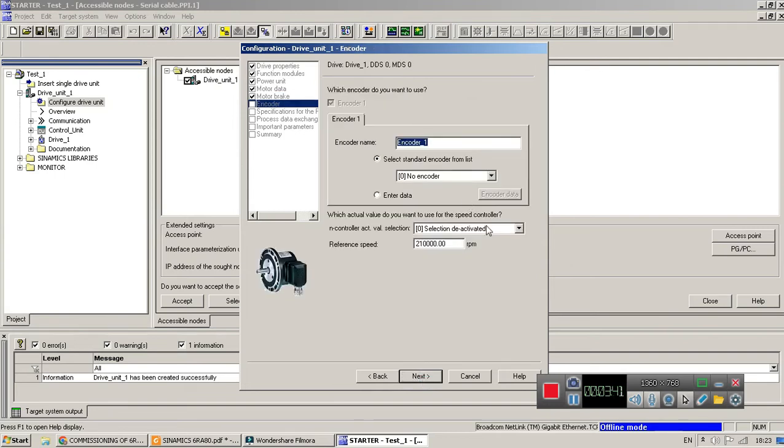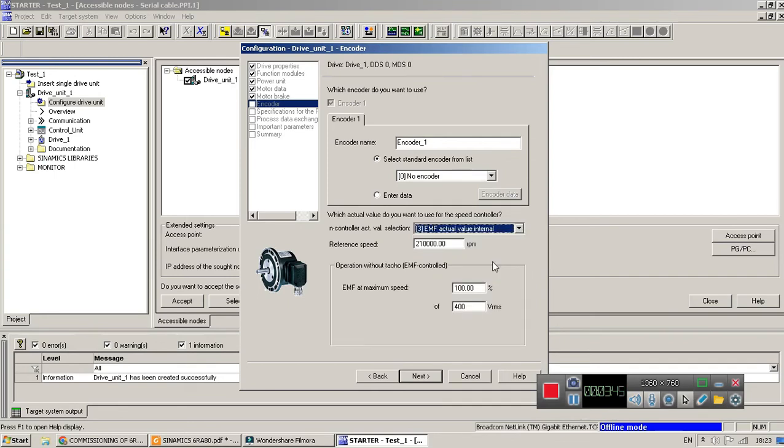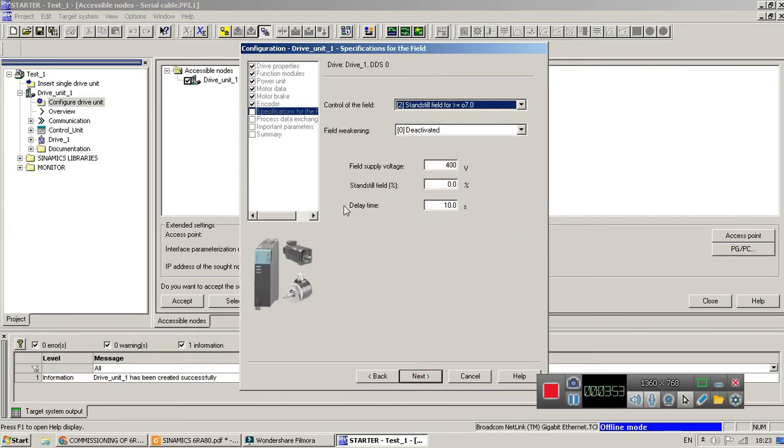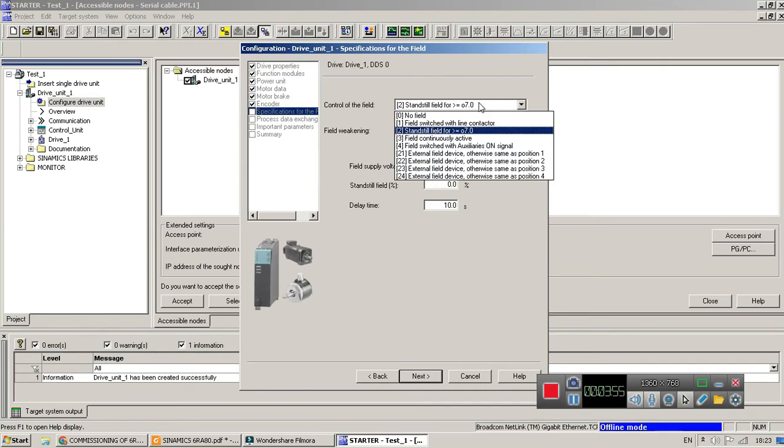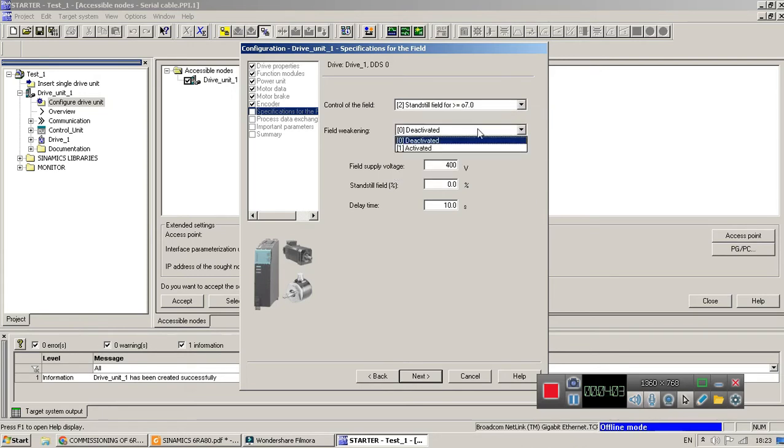Here we have selected speed feedback selection. Here I have selected EMF and the RPM of the motor, for 1500 let's suppose. Go to the next. And then standard field or field continuously active. Select according to your application. Field weakening according to your application.